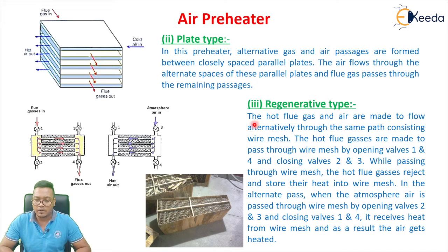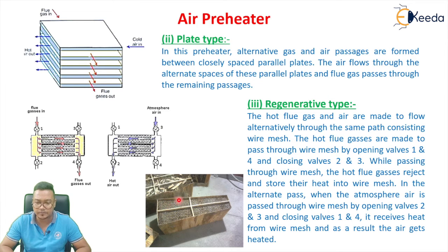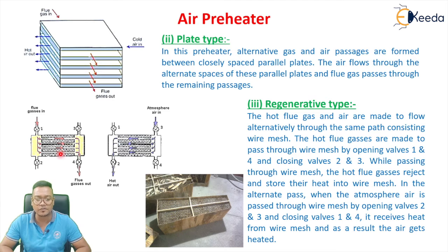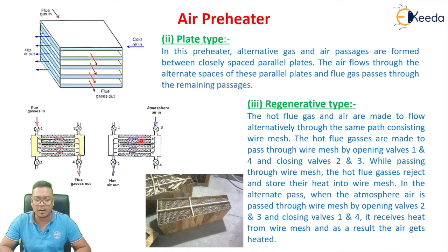In the regenerative type, the hot flue gas and air are made to flow alternatively through the same path consisting of a wire mesh or matrix. First, valves 2 and 3 are closed, and flue gas is passed from port 1 to port 4 — transferring heat to the wire mesh matrix. Then valves 1 and 4 are closed, and air flows from port 3 to port 2, recovering heat from the wire mesh. This is called the regenerative type air preheater.